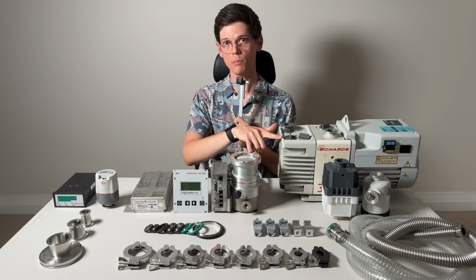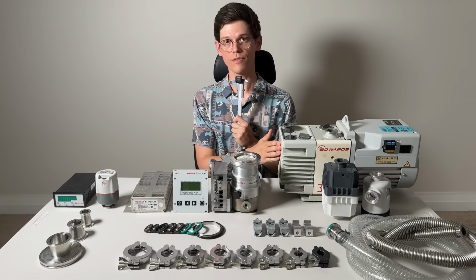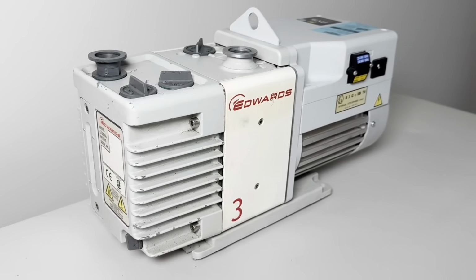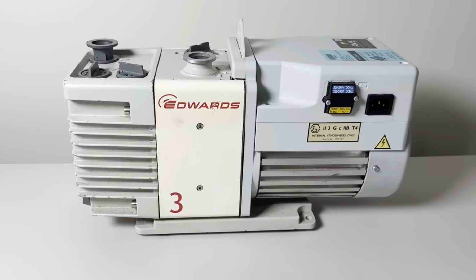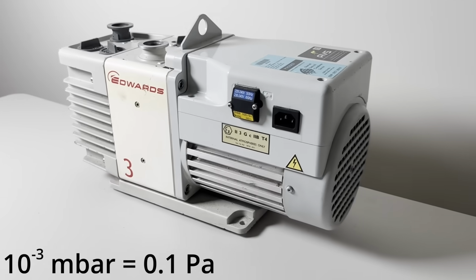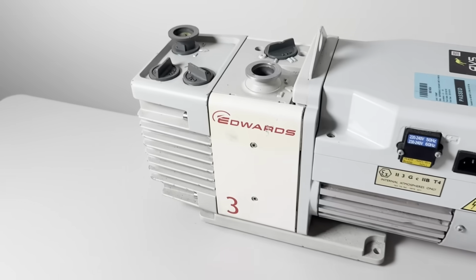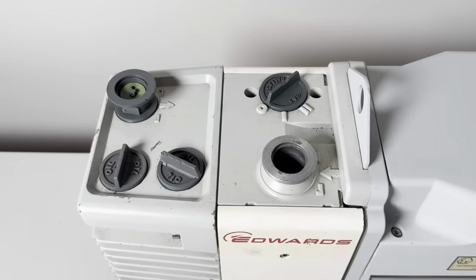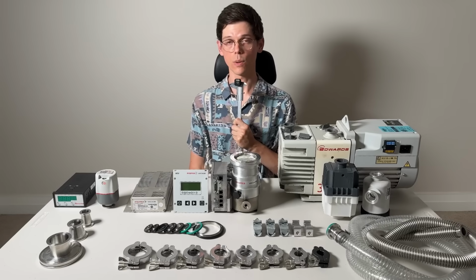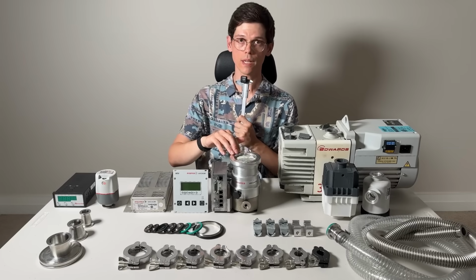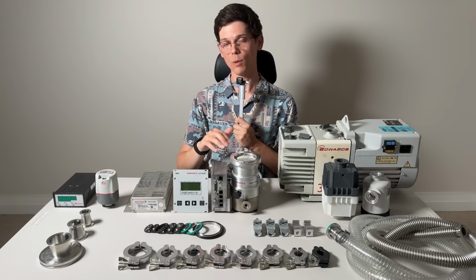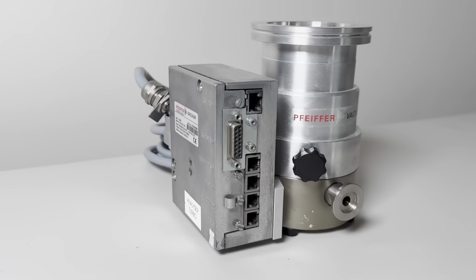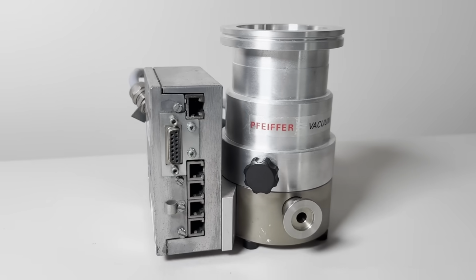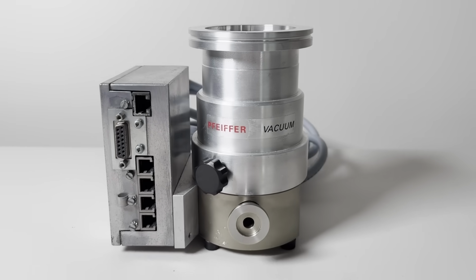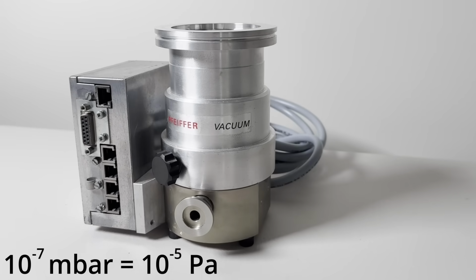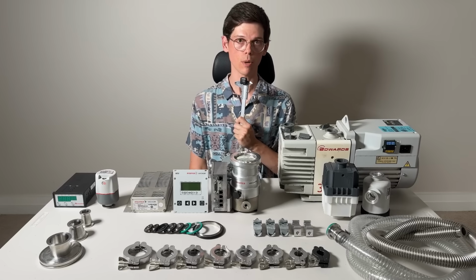Well, I got 2 pumps. The first is a rotary vane pump. It's full of oil, and it works from atmospheric pressure down to around 10 to the minus 3 millibar. Once you get there though, gases start behaving differently, and you need a different kind of pump to get to any lower pressures. That's where the second pump comes in. It's a turbomolecular pump. It uses a different mechanism from the rotary vane pump, and theoretically it should be able to get us down to around 10 to the minus 7 millibar, which is good enough for an electron microscope.